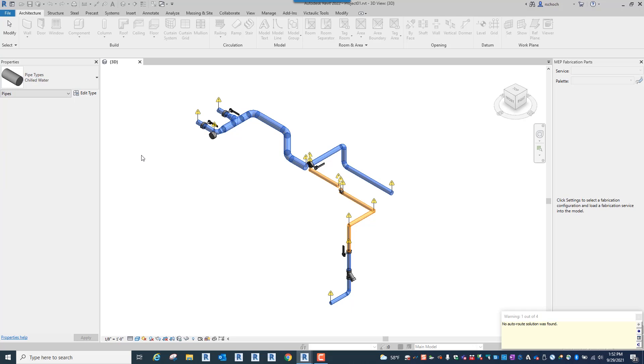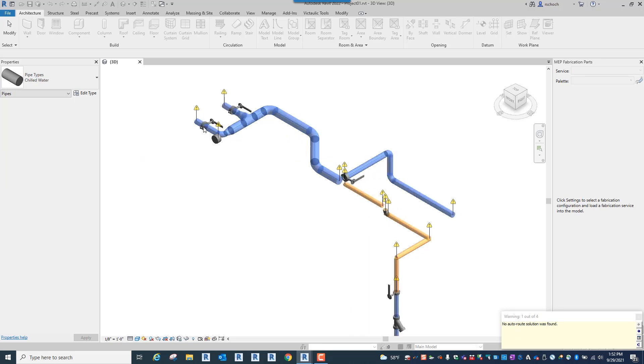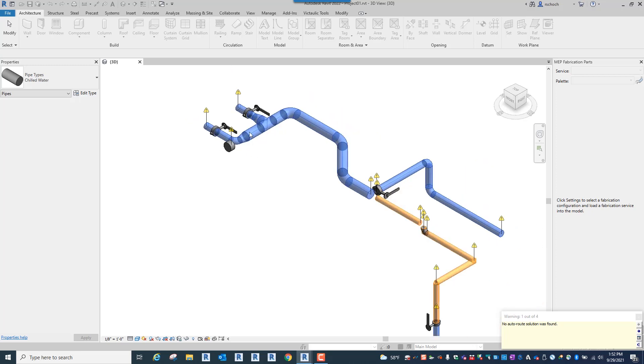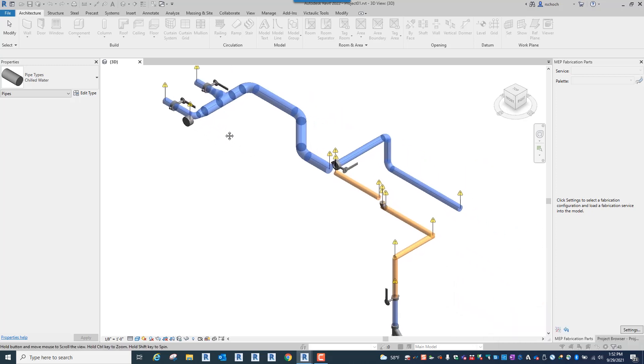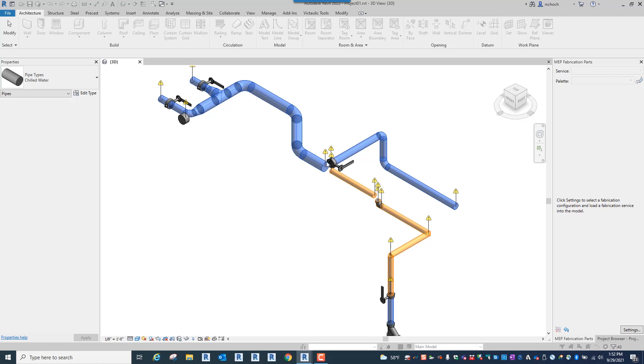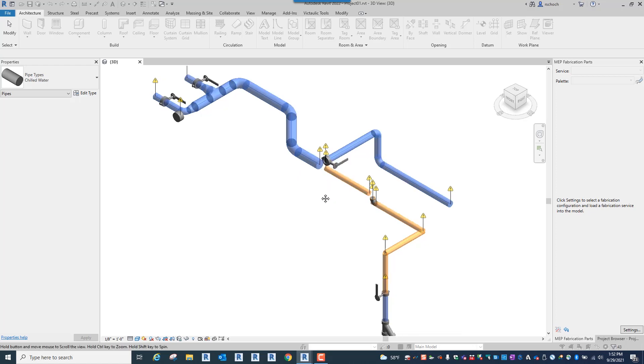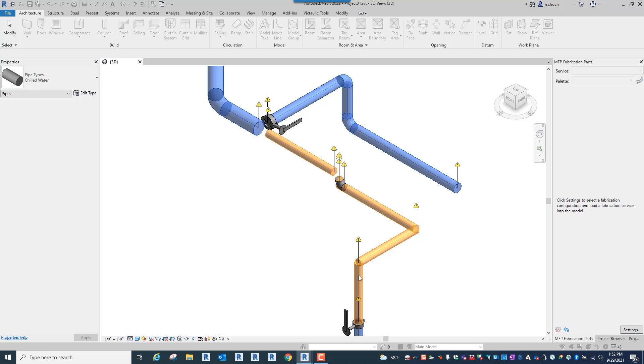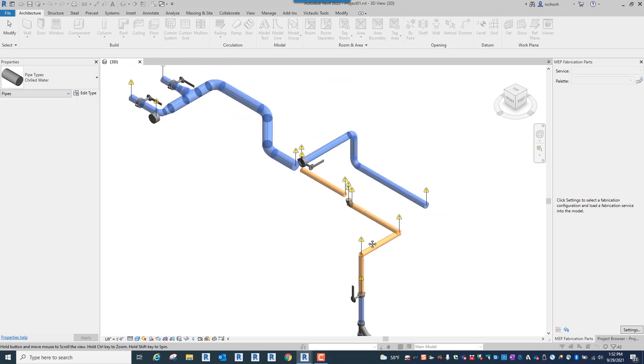And instantly we'll see there's an error message, which isn't the biggest issue. Really the biggest issue is you can see the disconnects that all just showed up. Here for some reason there was an additional elbow reducer put in and that tee was deleted so now that line isn't consistent. In here you can see the tee and reducer was deleted and the valve was disconnected. Here it broke at this offset or drop and then from there on out the piping just failed.